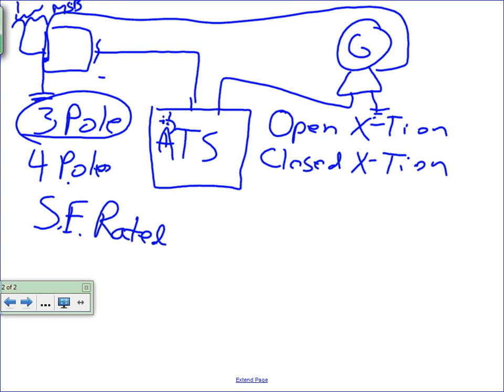Yeah. I think that kind of covers it for transfer switches. I'm pretty sure. Now, obviously, off of that, we're going to feed your main distribution panel. And again, depending on what all your loads are, because at this point I don't know if you know what your loads are in those panels. If it's got maybe one large breaker, 200 amps, something like that, and the rest are 100 amps and less, we may make that an NQ, or we may make that an I-line panel.